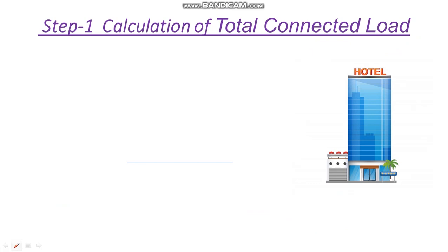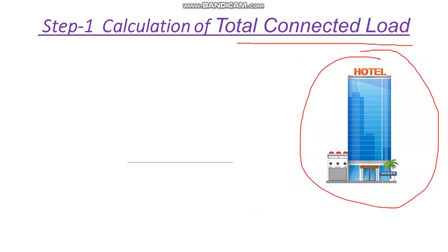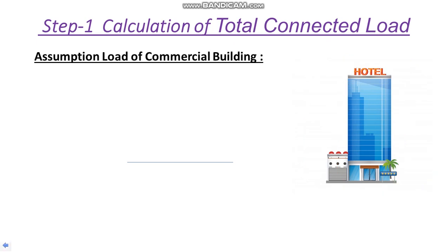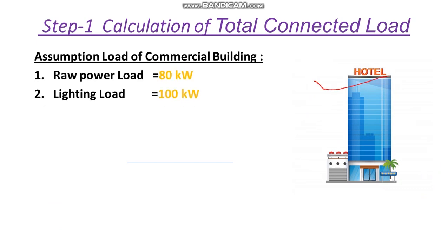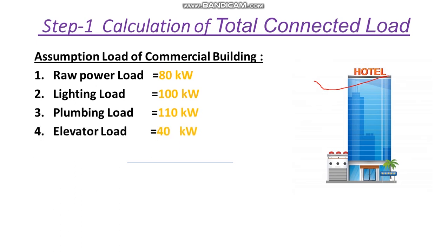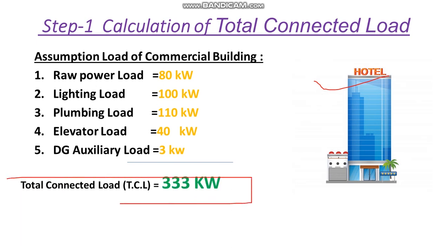Now let's follow these steps one by one. In Step 1 we have to calculate the total connected load. We are considering a hotel building as a commercial building example. The assumed loads are: raw power load 80 kW, lighting load 100 kW, plumbing load 110 kW, elevator load 40 kW, and DG auxiliary load 3 kW. Summing these gives a total connected load of 333 kW.